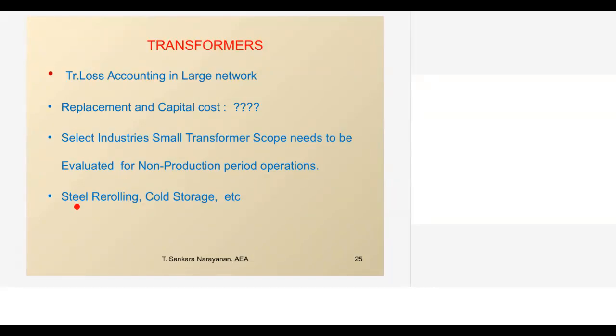This can come in a steel rolling, cold storage, even in a port operation, because there is no continuous ship. Throughout the year, you may handle 40 ships or 50 ships. Then all your major equipment and transformers are loaded. So in the non-shipping period, whether we can go for a smaller one. Some of these things have to be evaluated at the time of design stage. If the industry has funds for investment, then in some places we can go for a smaller transformer. So this is site specific and unit specific.